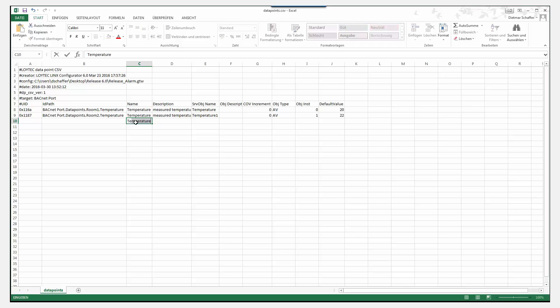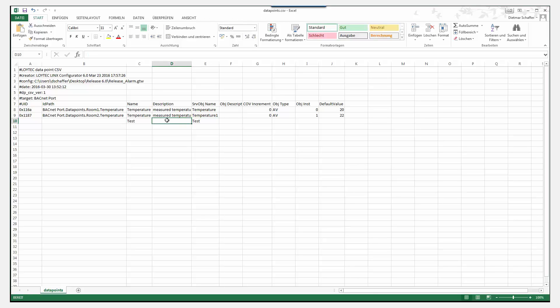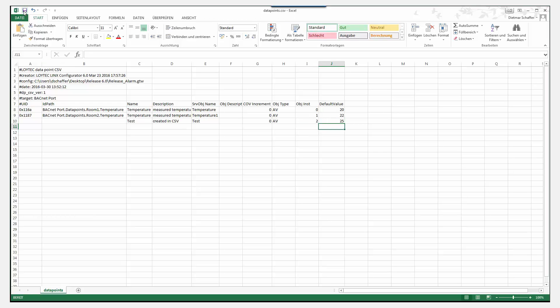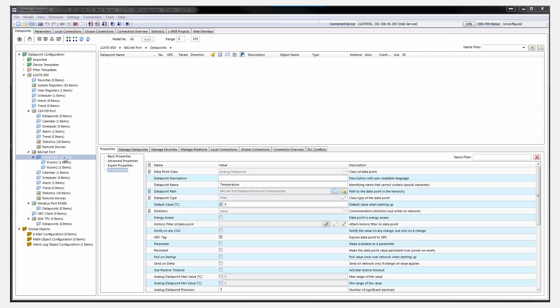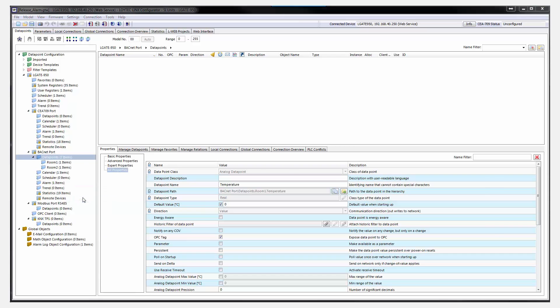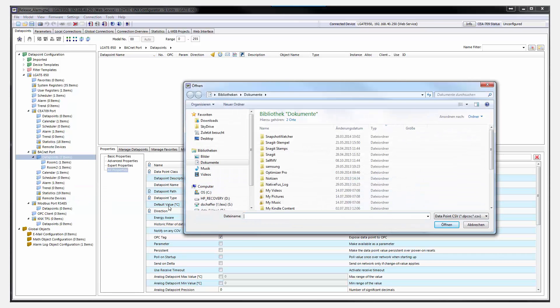Also, new data points can be created. By omitting the identification columns like UID and IDPath in the CSV file, the create mode is active when importing the data point CSV. Data points are created relative to the folder on which the import was started.